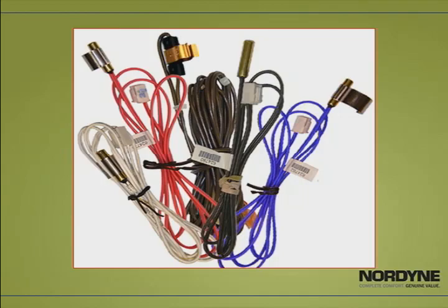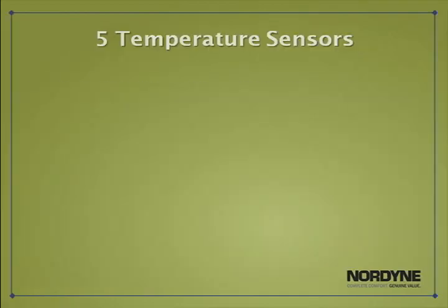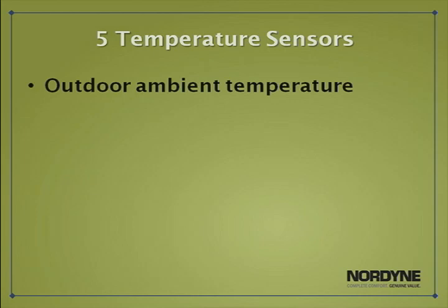The condenser has a total of 5 temperature sensors. The first is the outdoor ambient temperature sensor. This is used for defrost control, as well as helping control the system operation during minimum and maximum temperature environments. The minimum operating temperature in the heat mode is 0 degrees Fahrenheit, and the minimum temperature for cooling mode is 50 degrees Fahrenheit. The maximum operating temperature for cooling mode is 125 degrees.